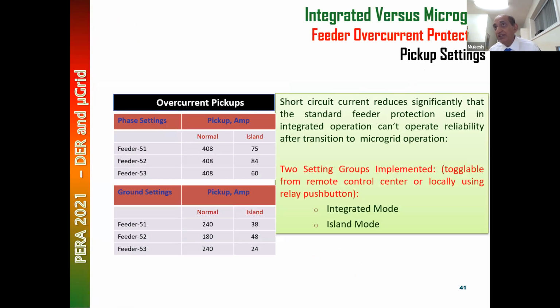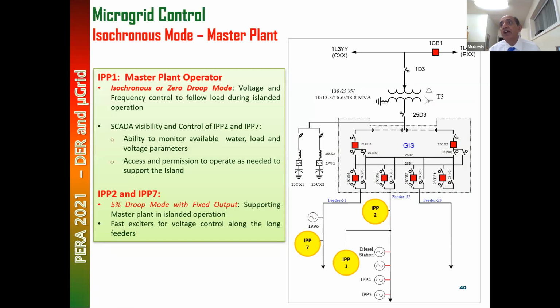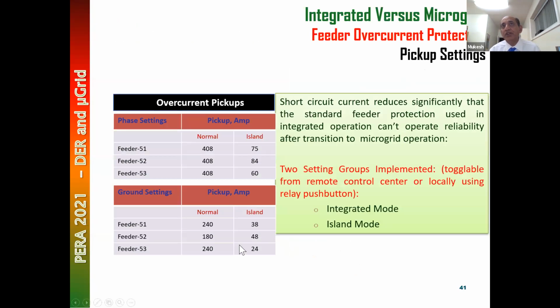Now, the challenge was that the fault levels are very low. The fault levels are very low because this is a very long, 52 kilometer feeder. Fault levels are very low in a microgrid mode and connected mode. So we have used 2 sets of protection, normal and microgrid island. Look at the phase protection. Our standard phase protection pickup is 400 ampere. In a microgrid mode, we have only 75 ampere. And this switch happens through a SCADA system. We have a SCADA control in our control room, and we can switch it remotely.